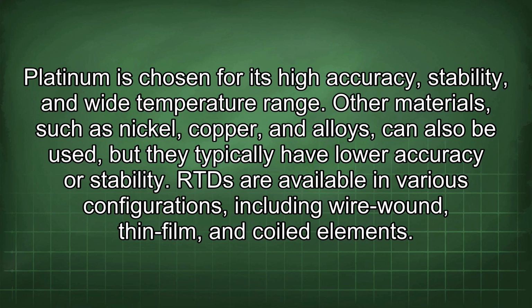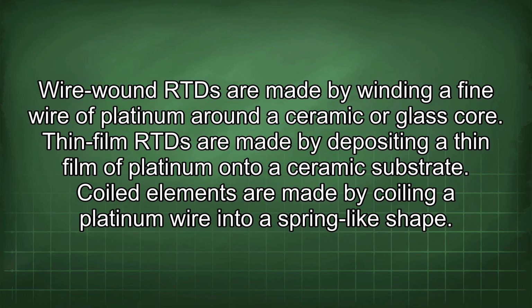RTD are available in various configurations, including wire wound, thin film, and coiled elements. Wire wound RTD are made by winding a fine wire of platinum around a ceramic or glass core. Thin film RTD are made by depositing a thin film of platinum onto a ceramic substrate. Coiled elements are made by coiling a platinum wire into a spring-like shape.